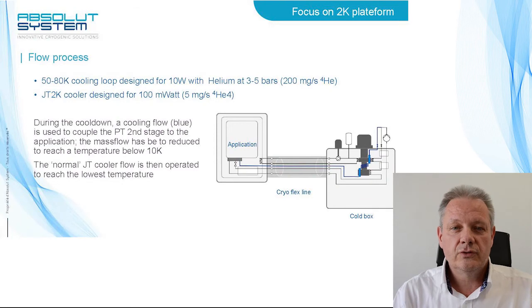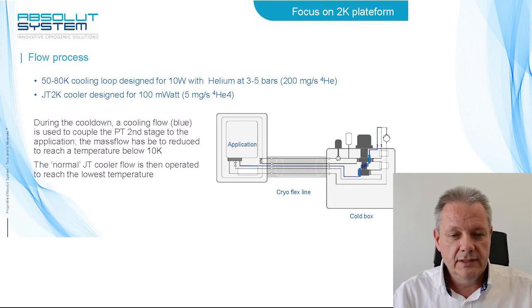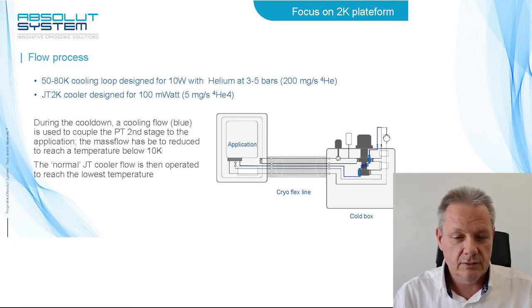The flow process is composed of two separated helium loops, both using helium-4. A 50 to 80K cooling loop uses a cryofan designed for 10 watts cooling power with a mass flow of 200 mg per second. A Joule-Thomson cooling stage uses a dry scroll pump designed for 100 mW at 2K with a mass flow of 5 mg per second. Due to the inversion temperature, a lower cool-down flow, in blue in the schematic, shall be used to couple the PT second stage to the application for pre-cooling to a temperature below 10K. Then the normal JT cooler flow can be operated to reach the lowest temperature.